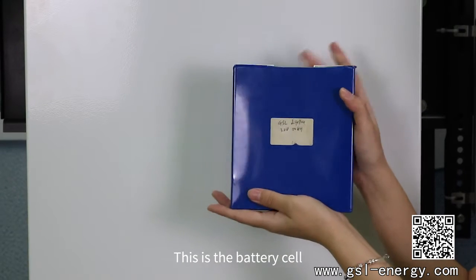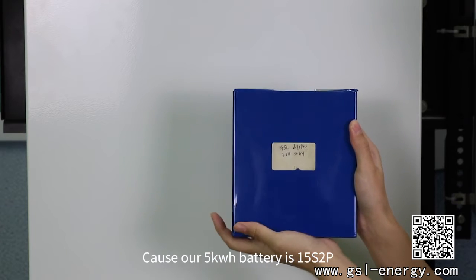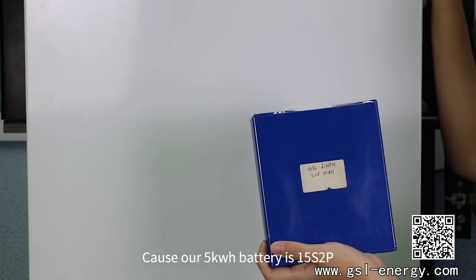This is the battery cell. It is 3.2 voltage, 50 amp hour. Because our 5 kilowatt hour battery is 15 series and 2 parallel, so there will be total 30 piece battery cells.